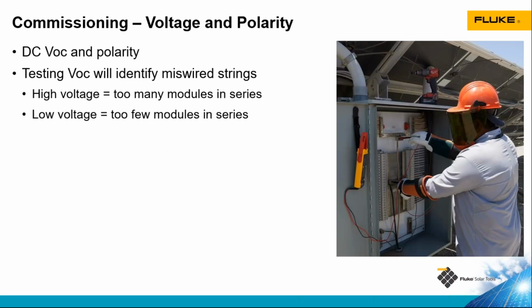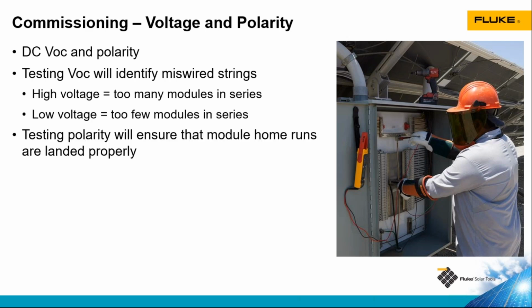During commissioning, we're going to do voltage and polarity testing. We'll figure out what the open circuit voltage of our modules are. We'll multiply that by the number of modules in the circuit and figure out the open circuit voltage of our string. And then we'll test for that voltage, making sure that the voltage isn't too high, which would indicate there are too many modules in the string, or too low, which would indicate there are too few modules in the string. And usually if you have high or low voltage, they're paired together because someone wired too many modules in one string and not enough in a different string.